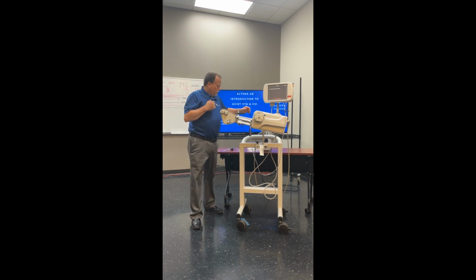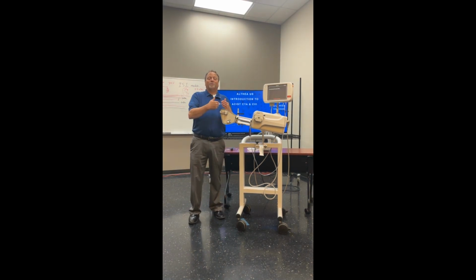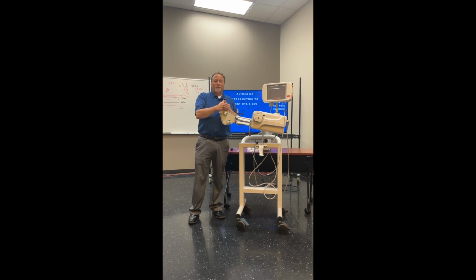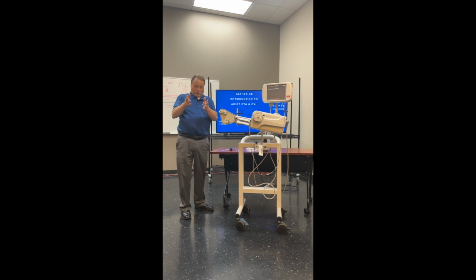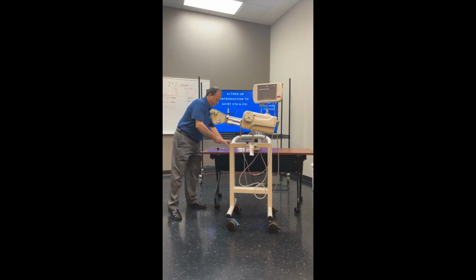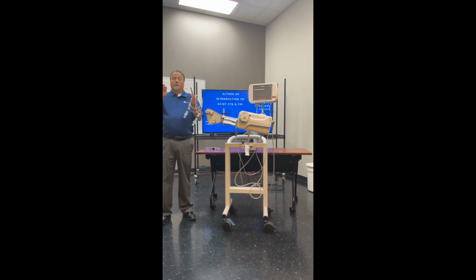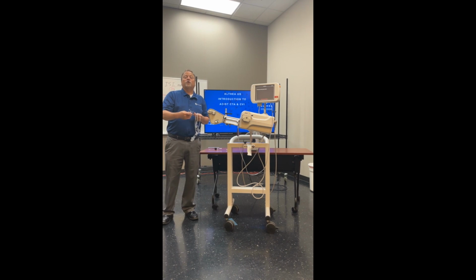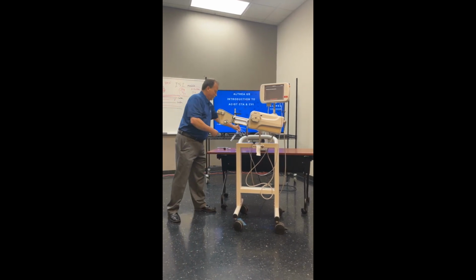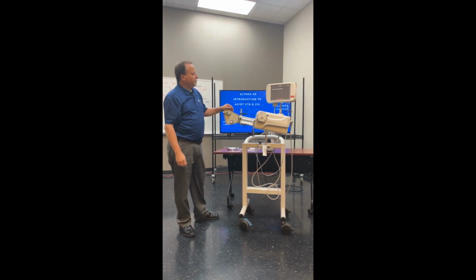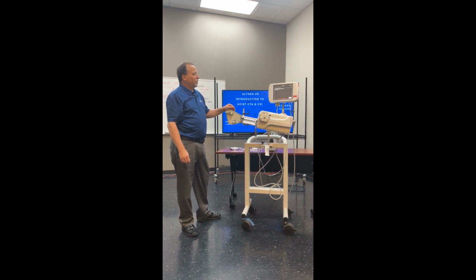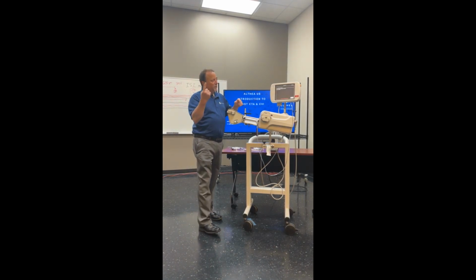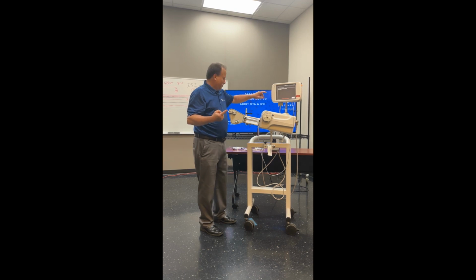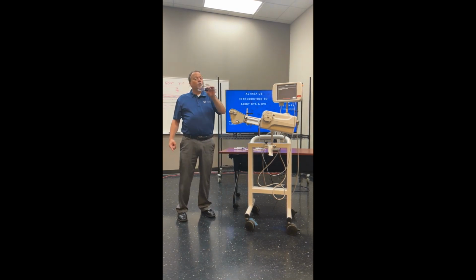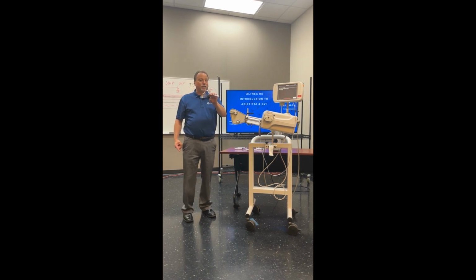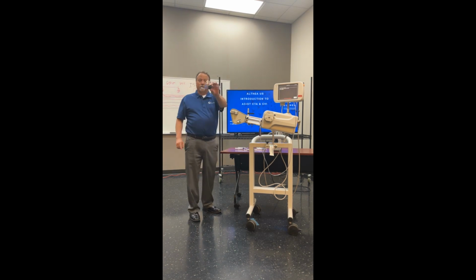As it's doing this, you have to basically go through an entire setup just to verify the operation of the system. And if you're the service technician, you have to use different jigs to basically cheat out the sensors to get to the point where you can actually test the injector. And one important tool that you have to have ready for you is a finger, because now it says load syringe assembly into chamber. If we were to load this syringe assembly, we cannot do a checkout or get to a point where we can actually do a checkout. So our finger is going to simulate the syringe.